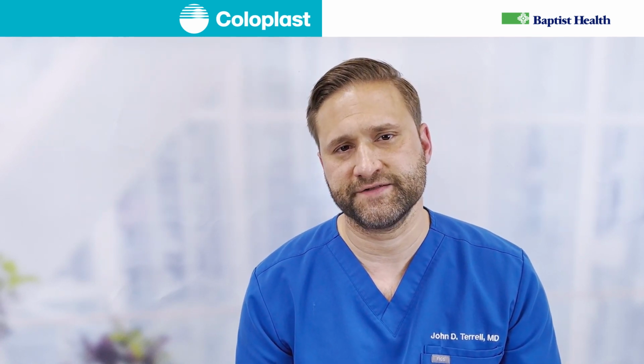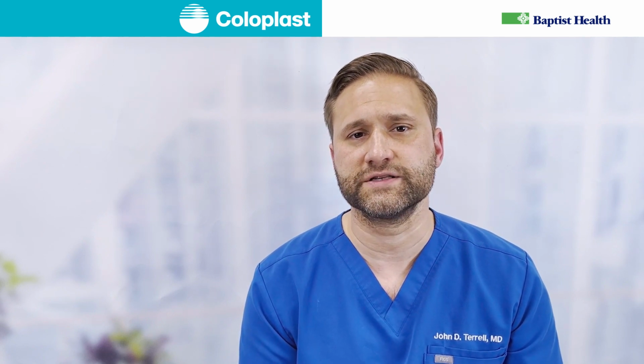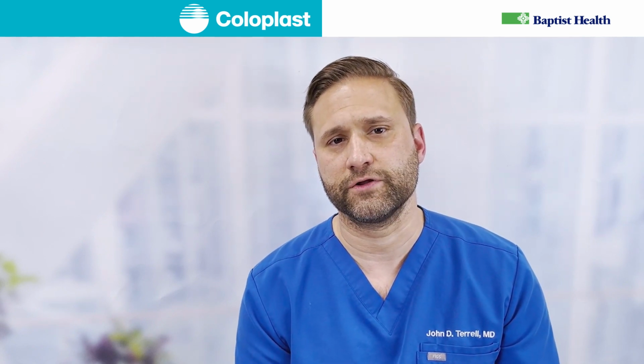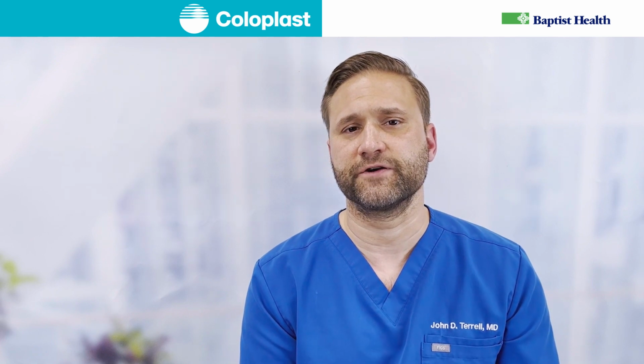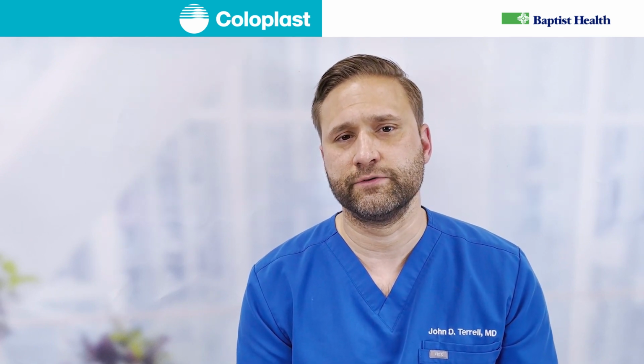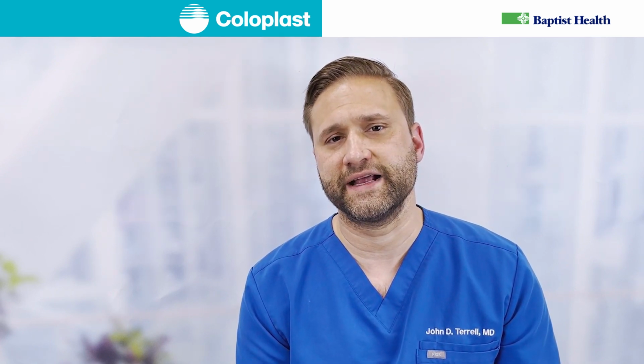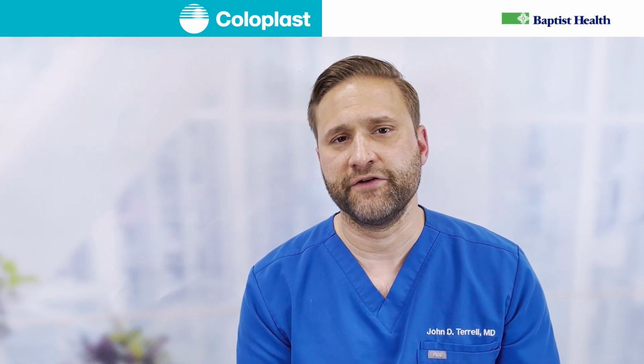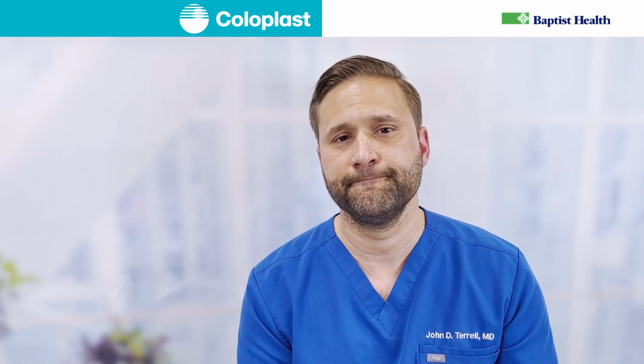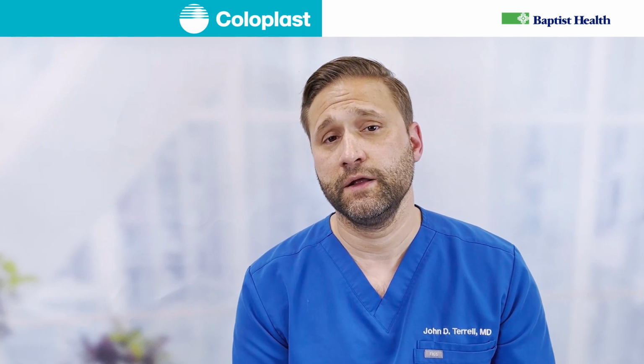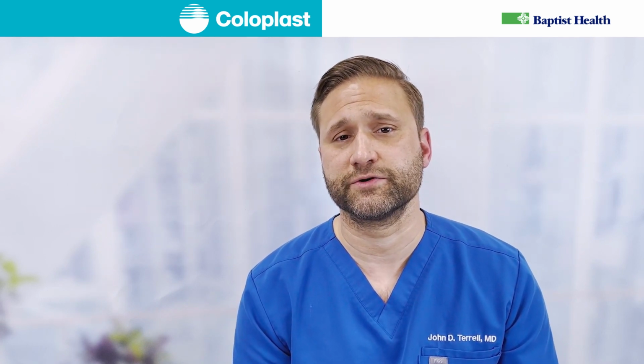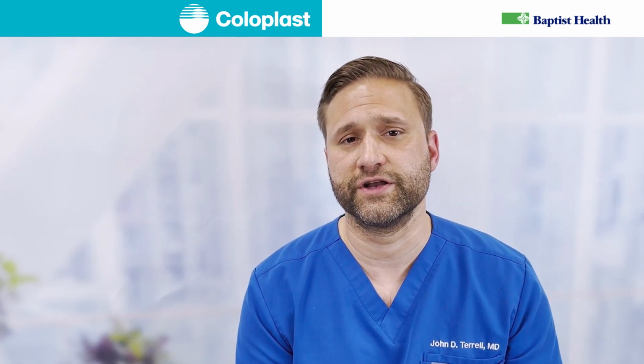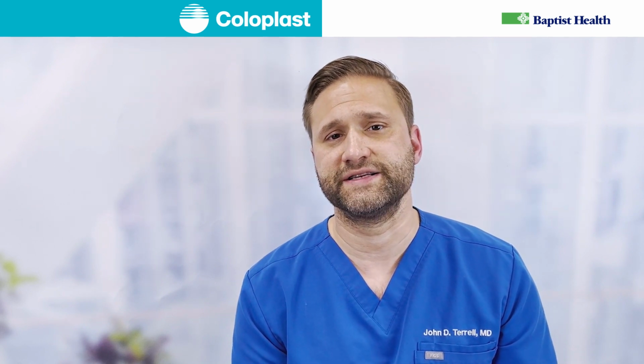Squeezing this pump transfers saline out of a reservoir that's also been implanted in a different concealed location. It transfers fluid out of that into cylinders that then become full of the saline. They also become rigid and firm and expand. When that's no longer needed, the button can be pushed, which allows a release valve to allow the fluid to transfer back out of the prosthesis into the reservoir.